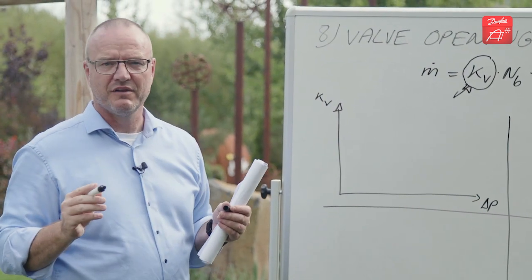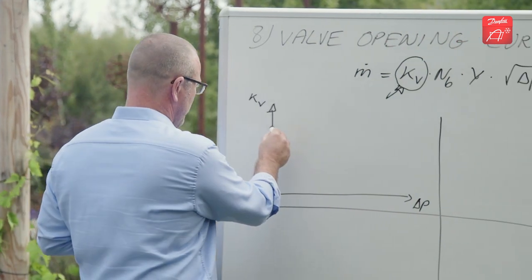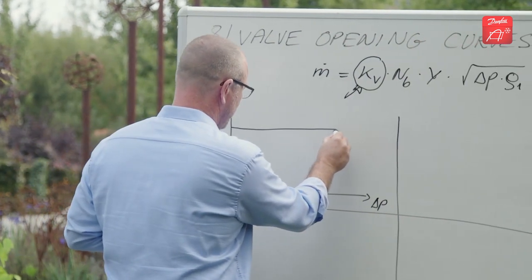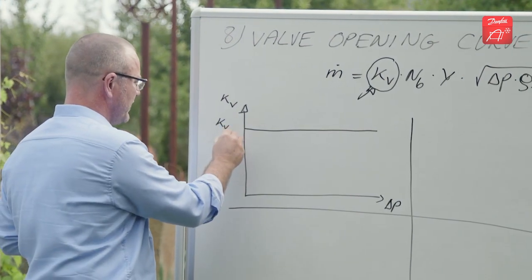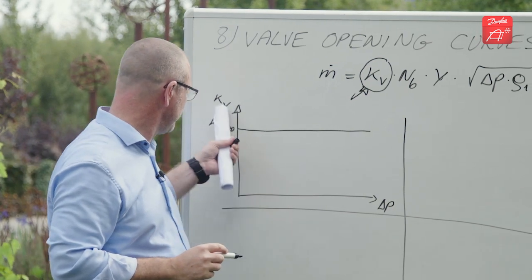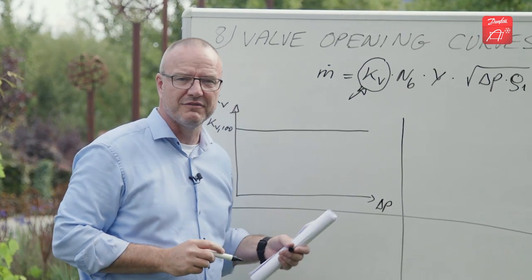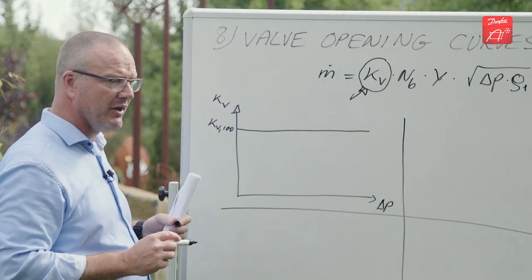If we start with the most simple valve types, that is the direct operated solenoids. When you open the valve you reach the fully open kV value immediately. The valve kV is not a function of the pressure drop across the valve. It's only a function of whether you have actually opened it or not.